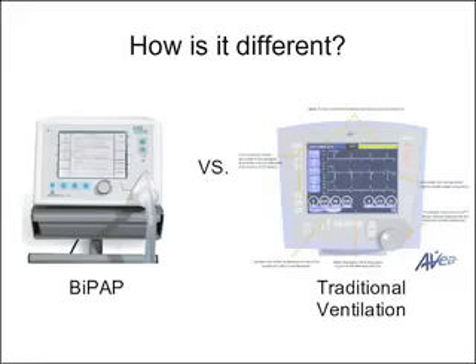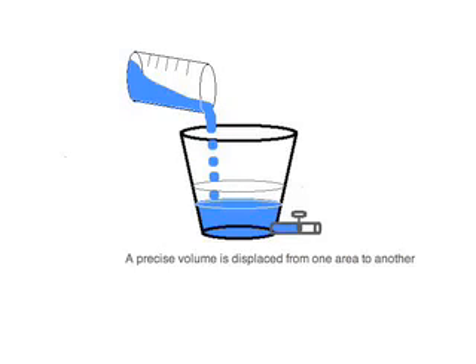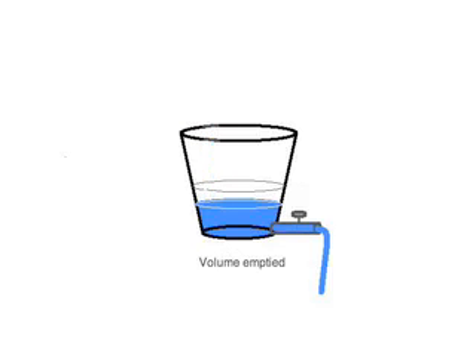While I was filming this, someone asked me, how does this differ from traditional ventilation? It sounds like the same thing that a ventilator does. And it is slightly different in that volume ventilation may be thought of as a pre-measured volume, like in this example, filling a bucket to a particular fill line. When the breath is over, the valve is opened. In the case of ventilation, an exhalation valve is opened and the volume is allowed to spill out. So volume enters a closed system until the valve is open, and then the precise volume leaves.